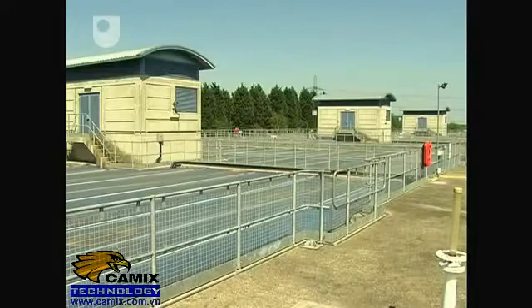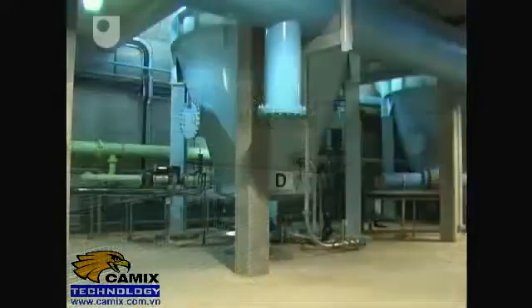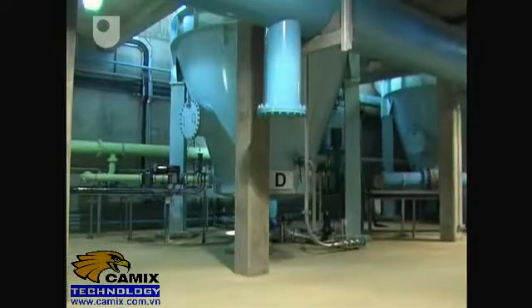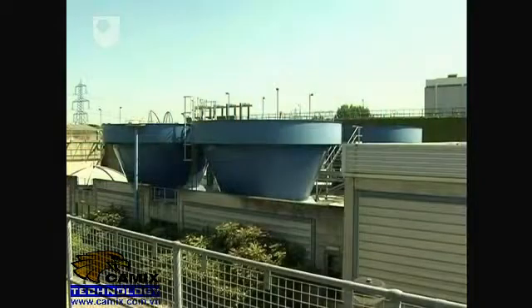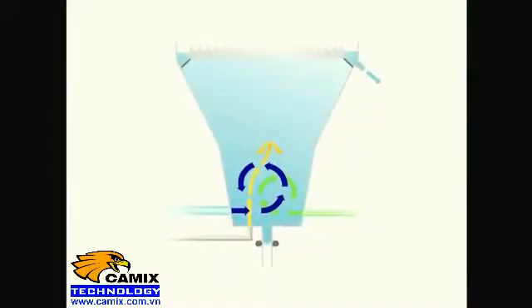The clarified water is pumped from the top of the pulsators into the bottom of large conical pellet softeners. Softening is necessary to stop an excessive build-up of scale on domestic appliances such as kettles and irons. In the softening process, the hard water is mixed with a calcium hydroxide solution and then it rises through a blanket of silver sand.